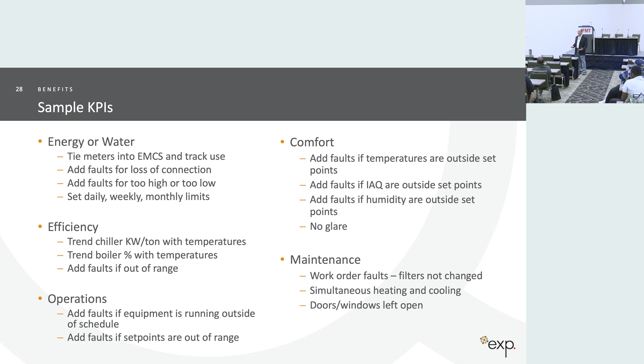If you're measuring lighting, you can define whether there's a glare instance, and maybe that's an issue that needs to be addressed. And then within maintenance, you have a work order system. So if your filters are not changed regularly, you would get a fault. Simultaneous heating and cooling is good to catch, or if doors or windows are open. You don't want your HVAC system working full, trying to maintain a space when the doors or windows are open. Do you try to monitor things like open windows? Oh, yeah. What sort of sensors would you use? They have a magnet, it's a little end switch, just a simple electric device. But when that frame comes off, it'll know. It's kind of the same thing they use when you come into a space. It tells you whether the door is held open.